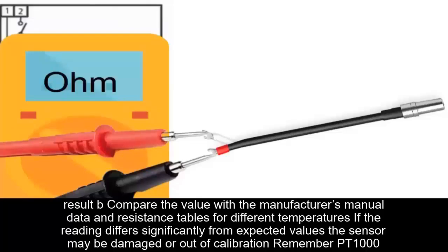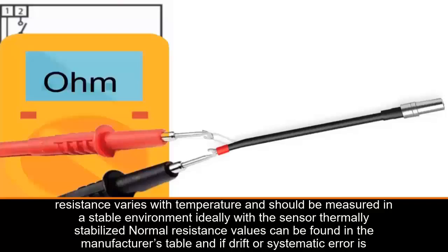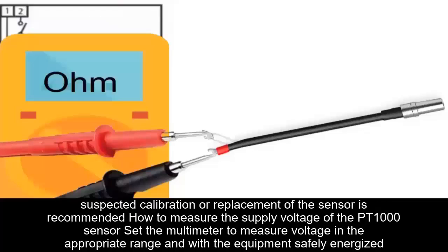B. Compare the value with the manufacturer's manual and resistance tables for different temperatures. If the reading differs significantly from expected values, the sensor may be damaged or out of calibration. Remember, PT1000 resistance varies with temperature and should be measured in a stable environment, ideally with the sensor thermally stabilized. Normal resistance values can be found in the manufacturer's table, and if drift or systematic error is suspected, calibration or replacement of the sensor is recommended.